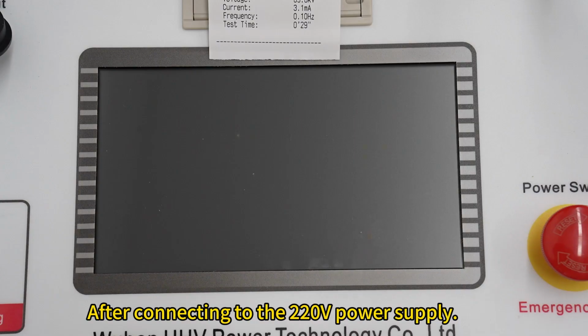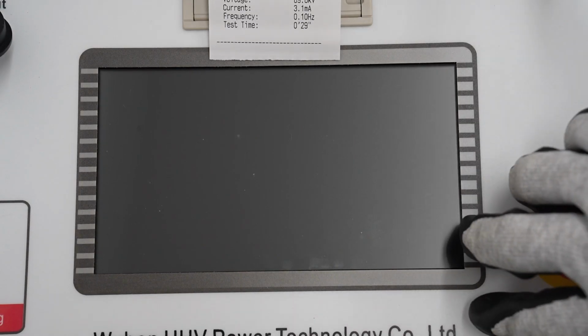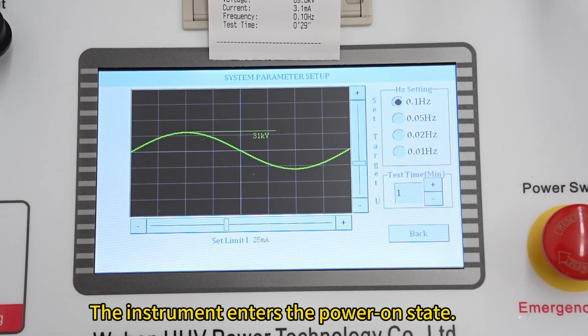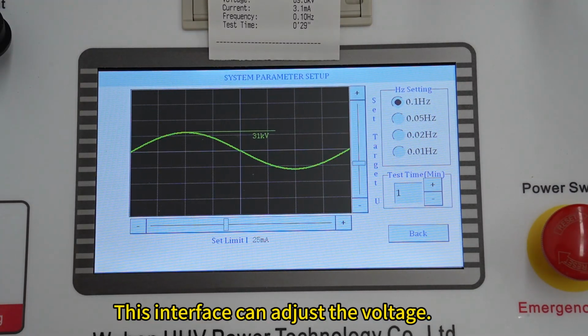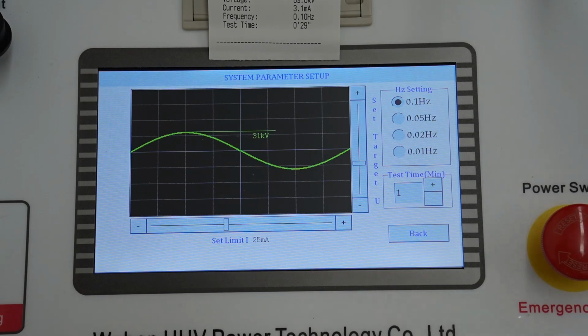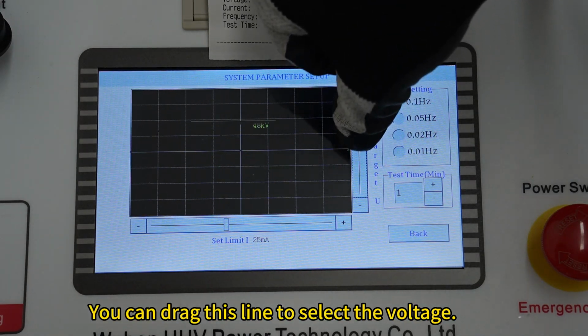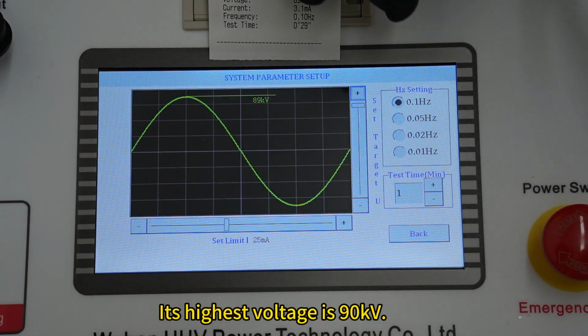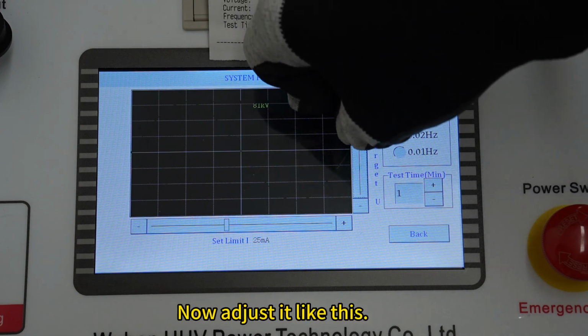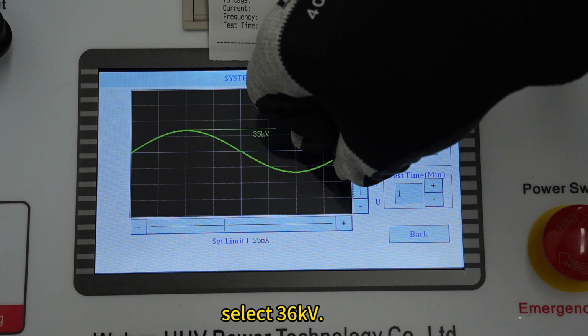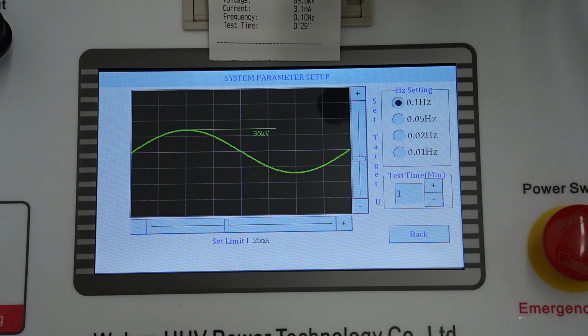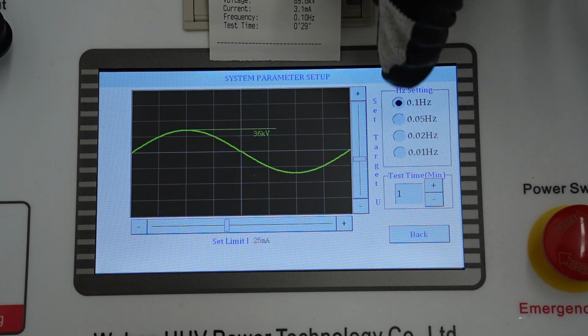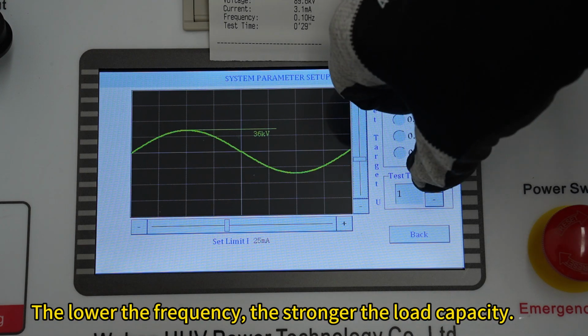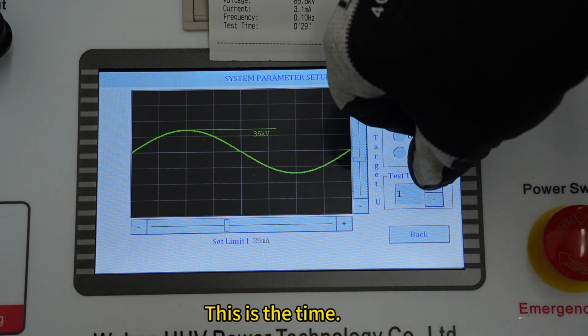After connecting to the 220 volts power supply, turn the knob. The instrument enters the power on state. This interface can adjust the voltage. You can drag this line to select the voltage. Its highest voltage is 90 kV. Now adjust it like this. Because it is a demonstration experiment, select 36 kV. Select the frequency here. The lower the frequency, the stronger the load capacity. This is the time. The time can be selected and added up and down.